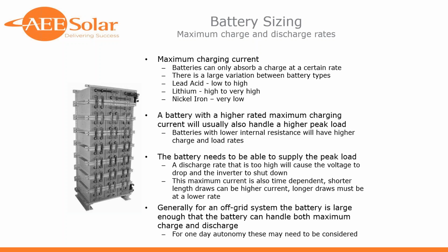And it's something that gets overlooked quite often, because somebody says, well, I want a 10 kilowatt solar array, grid tied, but I only need 5 kilowatt hours of backup battery. Well, that 5 kilowatt hours of battery is probably not going to be able to absorb 10 kilowatts of solar array charging it.